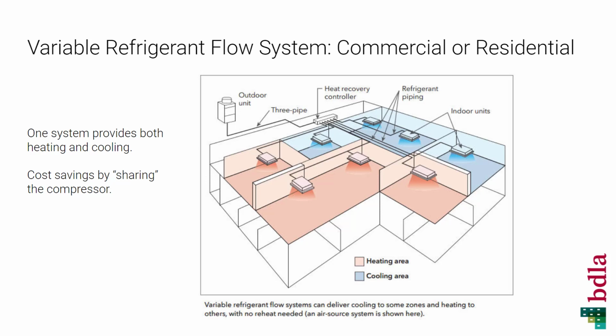Variable refrigerant flow systems are very common and getting more popular because it's an all-in-one solution. The outdoor units essentially operate as air source heat pumps, similar to the split system. But instead of having a single outdoor unit and a single indoor unit, a larger outdoor unit or many outdoor units paired together are connected with a whole array of indoor units throughout a building. This diagram shows 8 indoor units. There can be many more. The big benefits of VRF is that the outdoor unit and indoor units are connected by refrigerant piping, which is relatively small. And they're able to simultaneously heat and cool different zones in the same building.